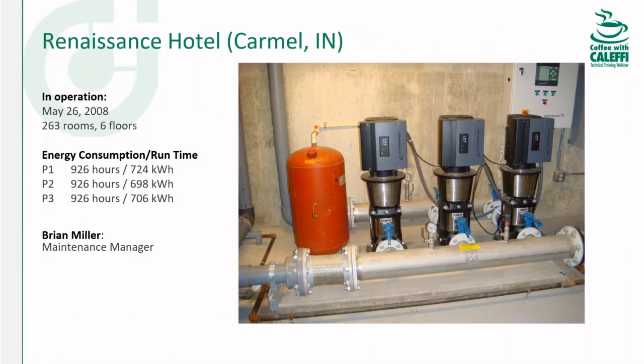Okay, so here's a booster at a hotel. Just some installation pictures here. Pop quiz. Who can tell me the critical component shown on this picture that wasn't on the previous slide? Something that should be on every single installation. So for those of you who got it, that would be the flex adapters. Every system needs that. They're critical for sure. And these are CRE 32 pumps, I think, 10 horsepower and about 160 gallons per minute nominal, each one.